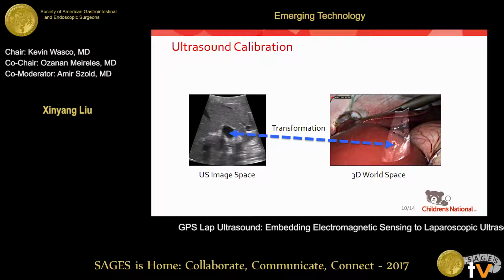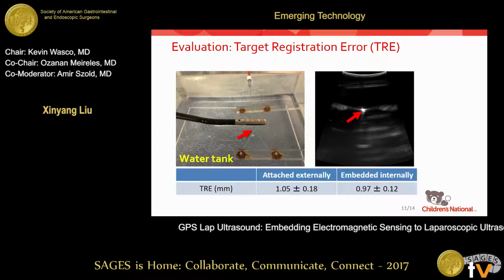The ultimate goal of why we want to track the ultrasound probe is that we want to generate a transformation from the ultrasound image space to the 3D world space. And this can be achieved by a process called ultrasound calibration. It is more straightforward and meaningful to evaluate the overall calibration accuracy, which incorporates EM tracking accuracy. And the metric we use is the target registration error.